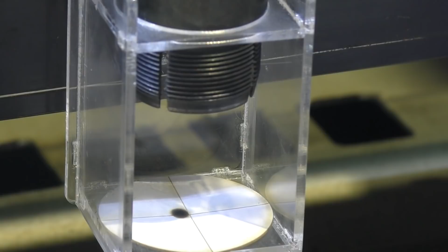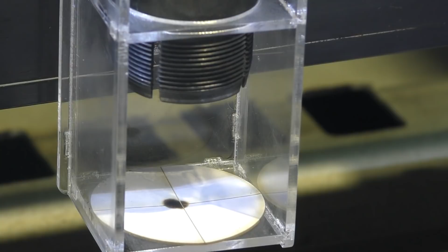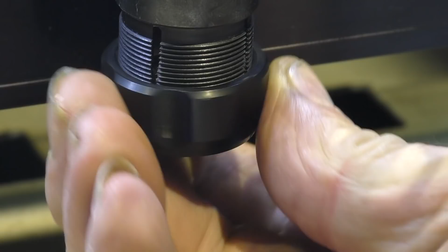Okay, so we've lifted the head up, and let's see what effect we've had on the position of the dot. Well, I can't say any more than it looks as though it's spot on. So what we do, we'll take that one out, we put another one in. Just make sure it's sitting in there snugly, and there we go. So now we know that the beam is hitting the sweet spot in there, going right down the central axis of the tube, and is vertical or perpendicular to the table. That's perfection as far as Z is concerned. Almost.